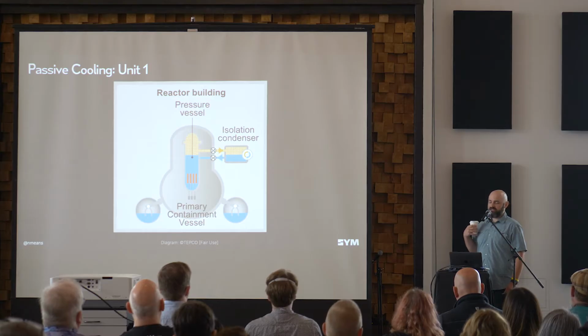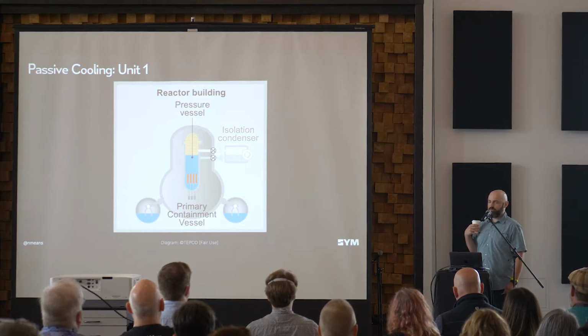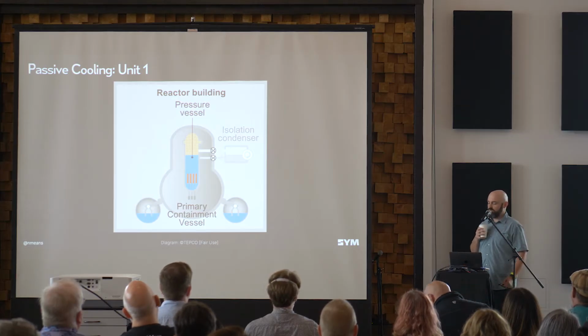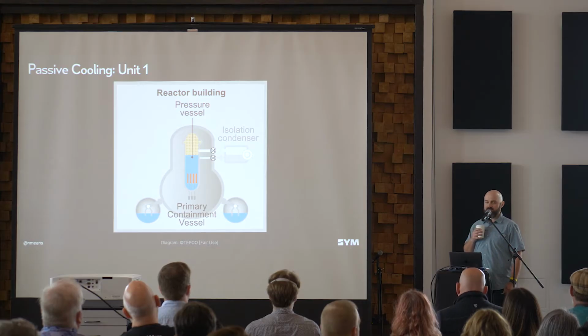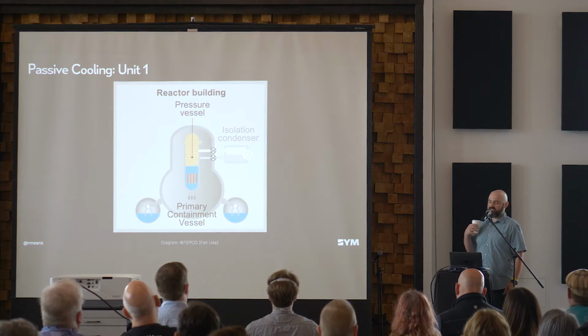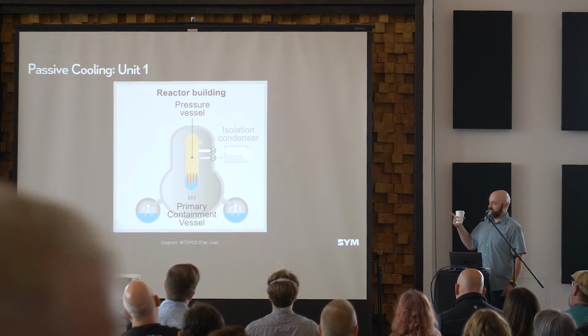They had just cycled the condenser back off at 3:34 p.m., 3 minutes before they lost power. The passive cooling systems in Unit 2 and 3 would keep them under control for the time being, but Unit 1, because of unlucky timing, was completely without cooling. Without cooling circulating to carry heat away, all of the water in the core will boil to steam.